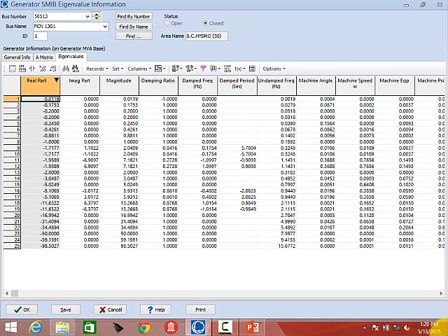That's what we're doing. In this case, this was an older WECC model, and it was one where there was actually a cause for this, and I'm going to show you how we can see the cause. So you look at these values. These are eigenvalues, damping ratio, the damping frequency in hertz. This is one where there's no oscillation. It would be decaying, or because it's positive, it's slowly growing.